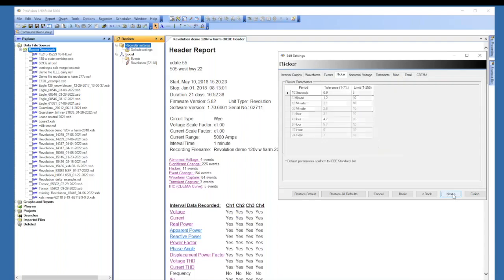The next tab is the flicker, and you can see the flicker report generated. This is based on the GE flicker curve. Don't really change anything in that. The abnormal voltage would be the next one. And this comes down and figures out what's closest to the nominal. And then you have a plus or minus high range and a plus or minus low range. And then your abnormal voltage report that gets generated over here tells you whether or not it broke out of those ranges.